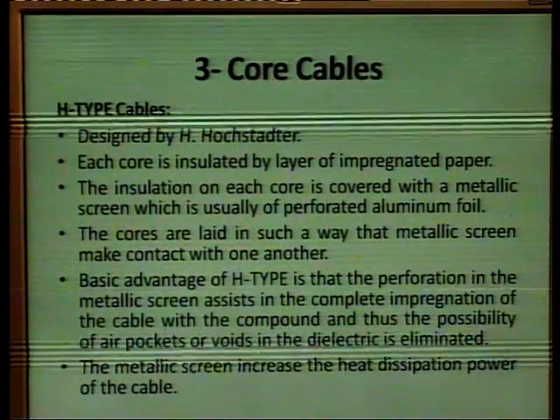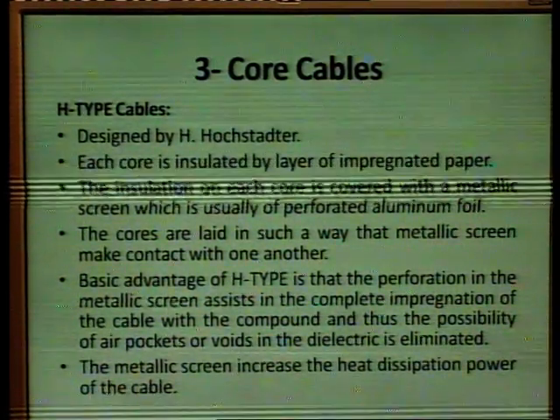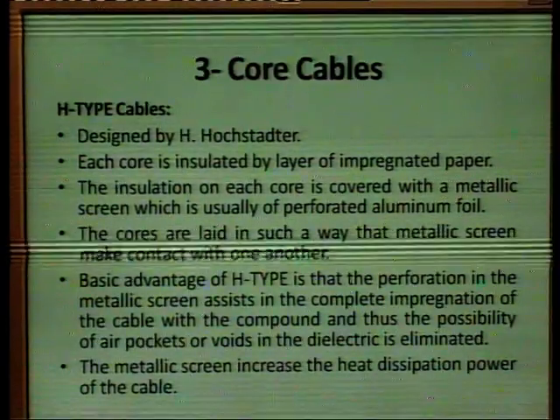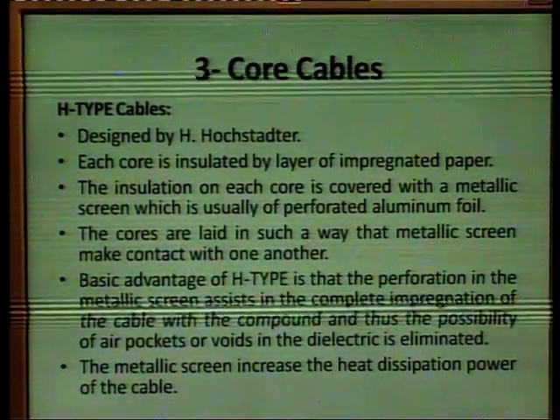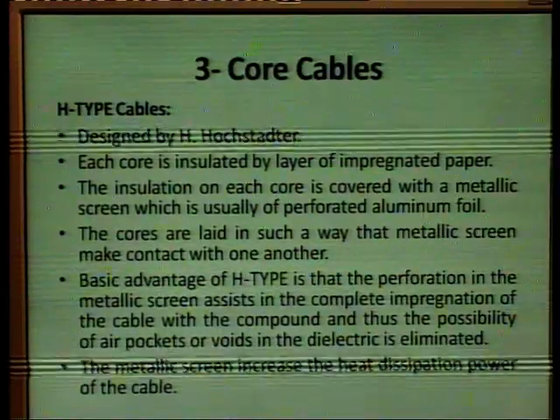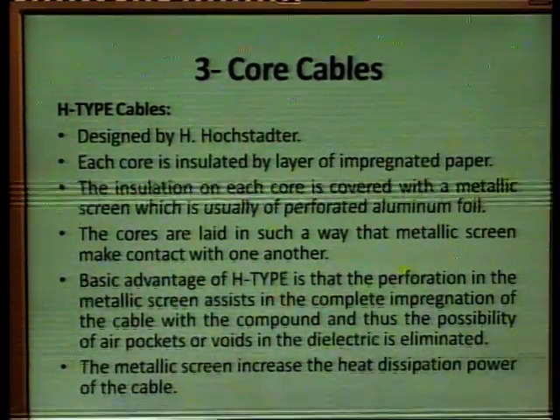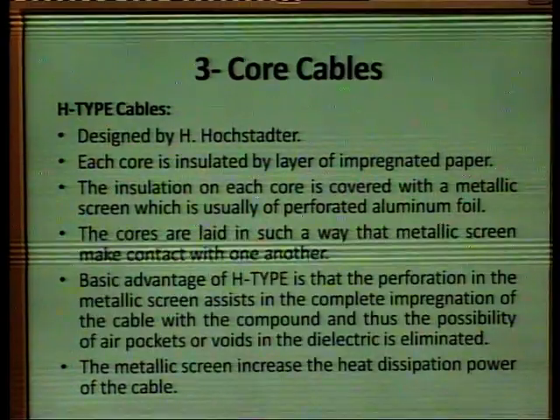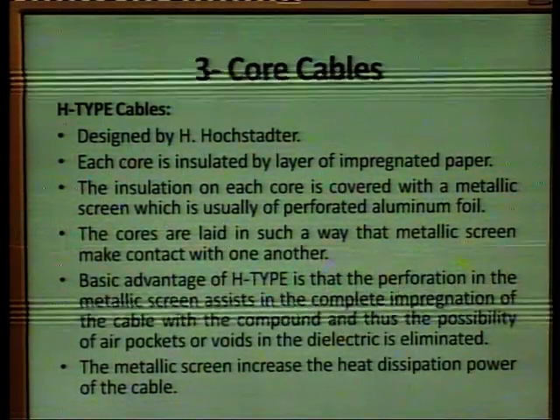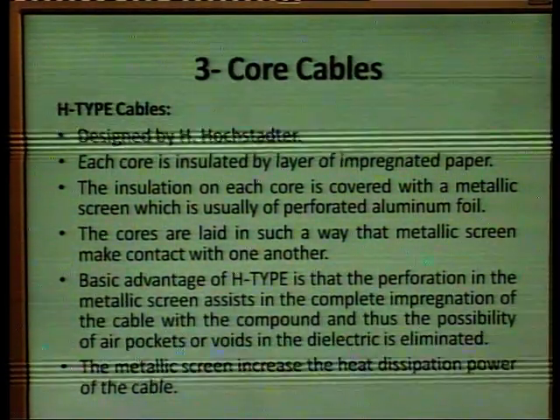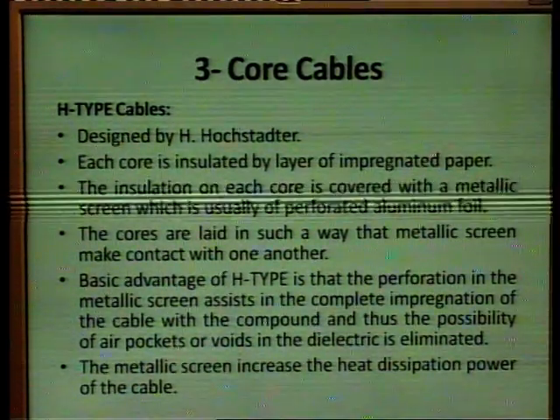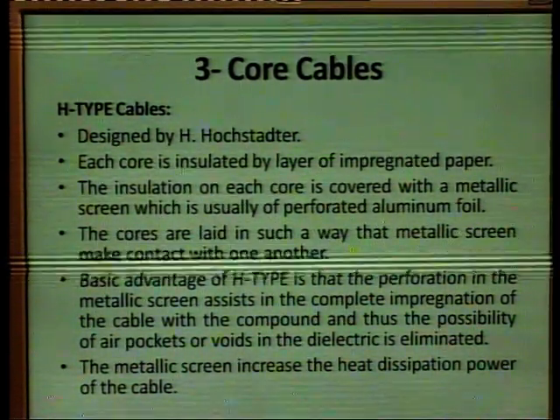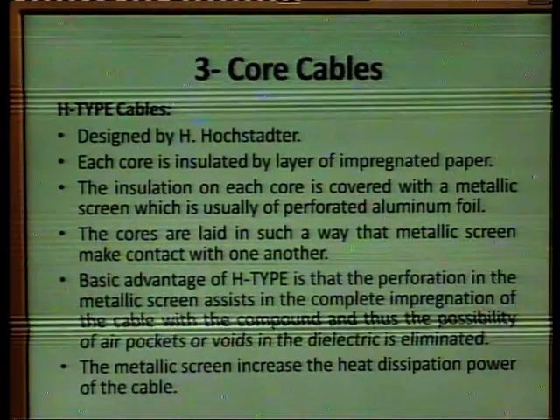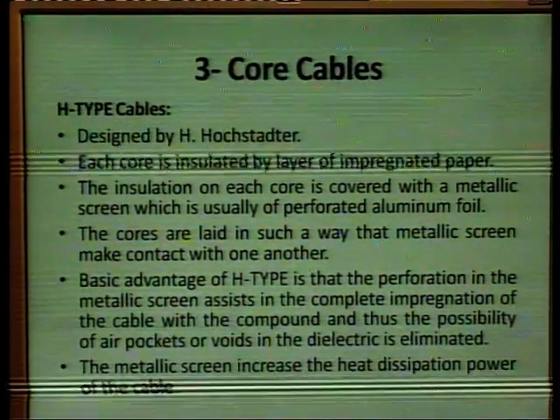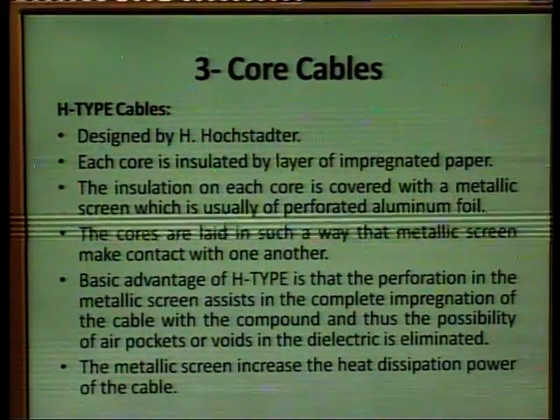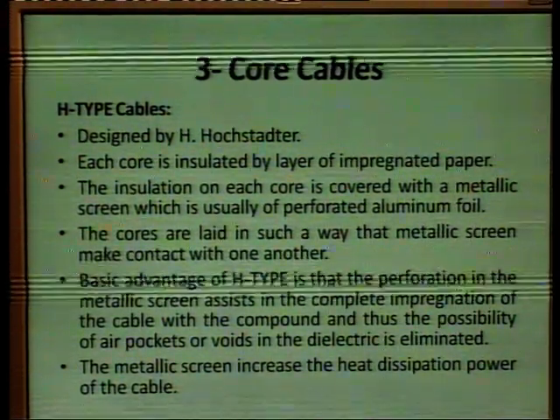The basic advantage of H type is that the perforation in the metallic screen assists in the complete impregnation of the cable with the compound, and thus the possibility of air pockets or voids in the dielectric is eliminated. The metallic screen also increases the heat dissipation power of the cable.